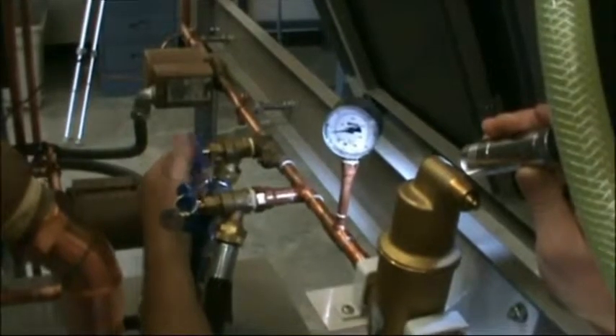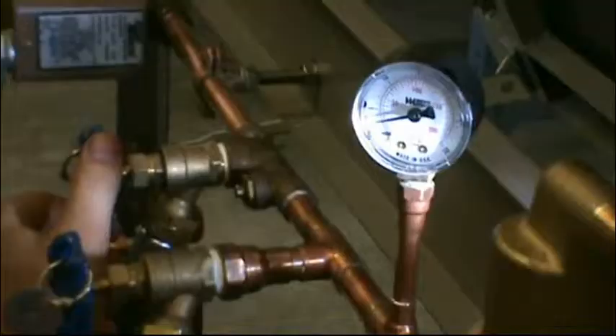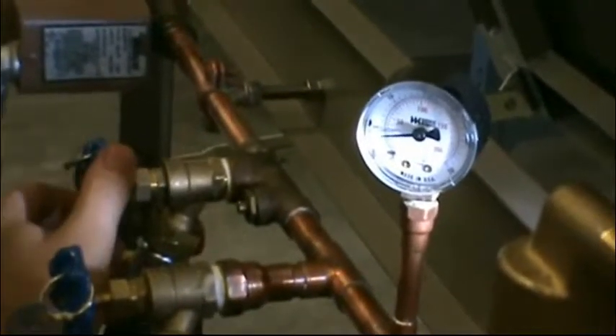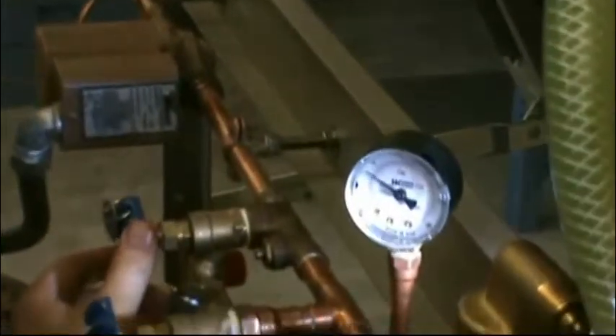So I'm going to keep going here until that pressure starts to... That pressure's coming up now. Pressure's coming up. Pressure's coming up. And as that pressure comes up, the flow should not change. The flow will still remain the same, and it is. Notice the flow has not gone down.